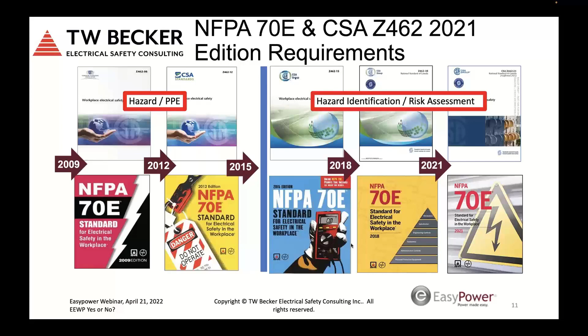The permit is a yes/no permission type document. Separate from the permit, even without one, you always have to have electrical hazard identification and a risk assessment completed, and the hierarchy of risk control methods applied by the qualified person to reduce risk if we're doing energized work. So energized work is authorized - it's just a matter of how the energized electrical work permit is interpreted.